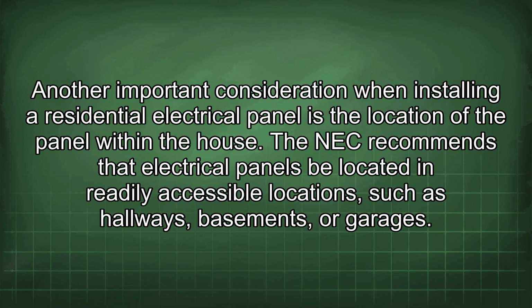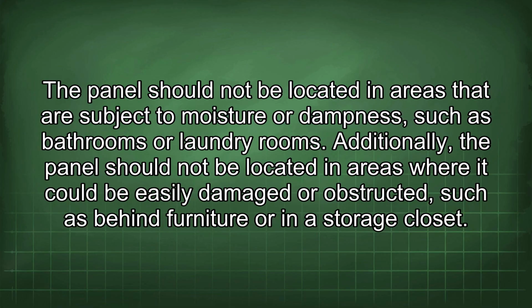Another important consideration when installing a residential electrical panel is the location of the panel within the house. The NEC recommends that electrical panels be located in readily accessible locations, such as hallways, basements, or garages. The panel should not be located in areas that are subject to moisture or dampness, such as bathrooms or laundry rooms. Additionally, the panel should not be located in areas where it could be easily damaged or obstructed, such as behind furniture or in a storage closet.